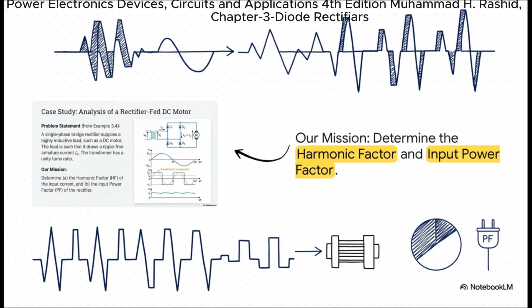We're going to analyze the rectifier-fed DC motor circuit from example 3.4 in our source material. Here's the mission: we've got a standard single-phase bridge rectifier feeding a highly inductive DC motor, and we know it draws a pretty much ripple-free current. Our job is to calculate two things: first, the harmonic factor, or THD, of the input current, and second, the final true input power factor.